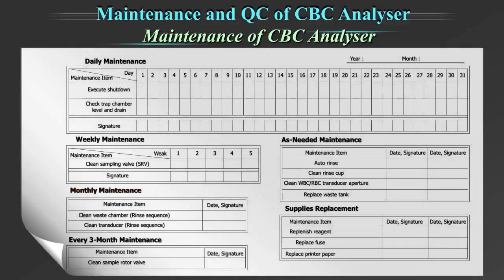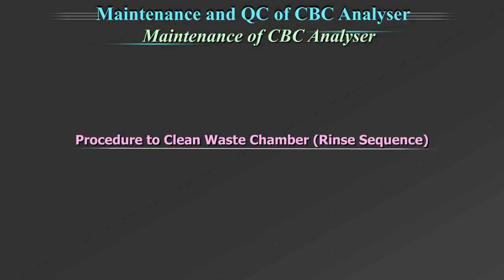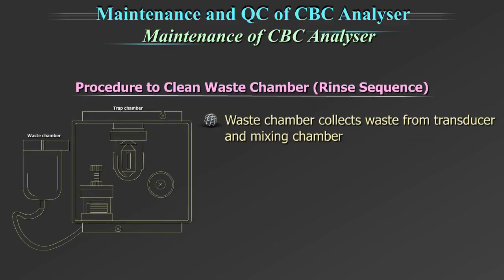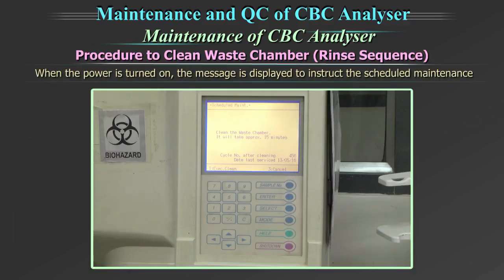Important monthly maintenance here includes cleaning of the waste chamber and transducer. The procedure to clean waste chamber. Waste chamber collects waste from transducer and mixing chamber. This part also requires weekly cleaning using partially automated process as the operator has to aspirate cleaning solution. When the power is turned on, the message is displayed automatically to instruct the scheduled maintenance on due date.